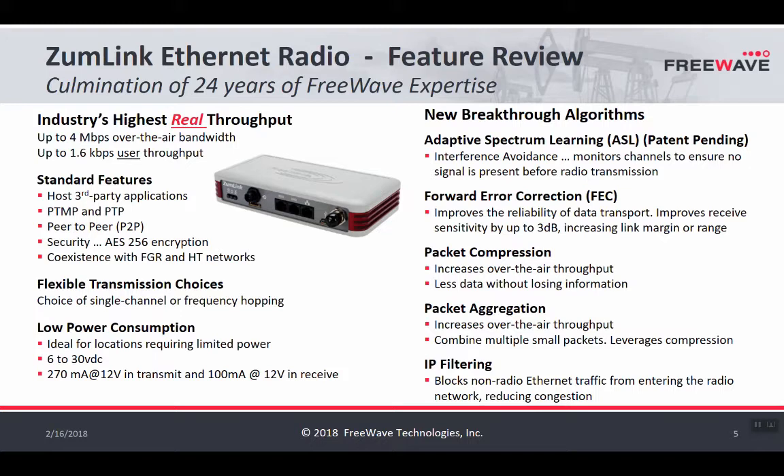In industrial spaces, power sources may not always be reliable — there may be battery backup or solar — so ZumLink was designed with low power applications in mind. You can review the power requirements on the spec sheet. New to the ZumLink platform is Adaptive Spectrum Learning, or ASL, which allows ZumLink to operate in congested environments. Using ASL, the radio listens before it transmits, ensuring there's a break in the airspace to get its message through. Forward Error Correction, or FEC, improves the reliability of data transport in congested and noisy RF environments by adding data to correct corrupted packets.